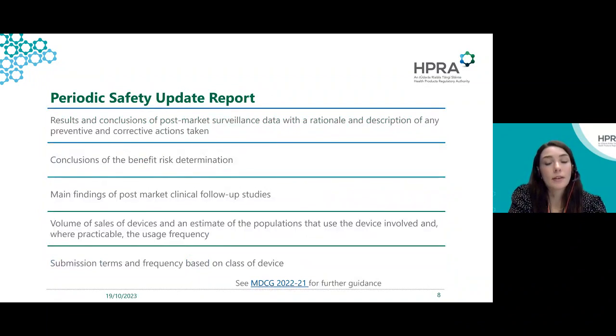Then the Periodic Safety Update Report, which is relevant for class 2A, 2B and 3 devices. It's where you'll document the results and conclusions of the planned analysis, whether corrective preventive actions were taken, any resulting changes to the benefit risk evaluation, outcomes of post-market clinical follow-up studies, and accurate information on the sales and usage of the device during the evaluation period.